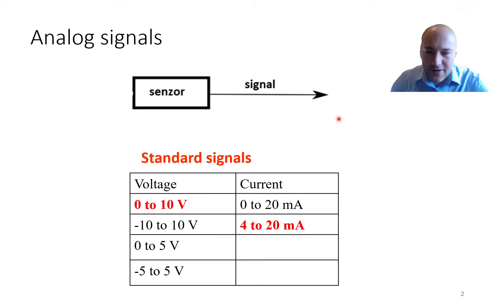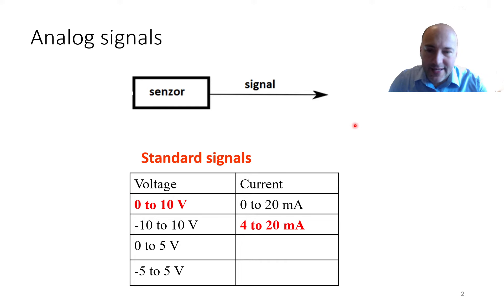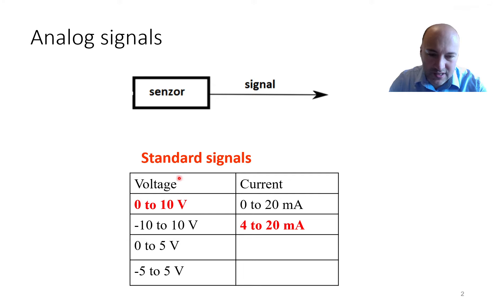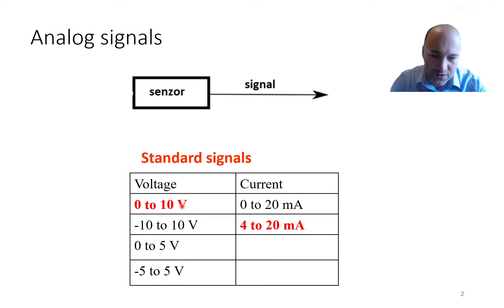We have defined ranges for these standard signals. One reason for standards is that we want to connect a sensor from one manufacturer to a controller system from a different manufacturer. The most common standard signals are summarized in a table. For voltage, the most common signal is 0 to 10 volts, and for current, the most common is 4 to 20 milliamperes.